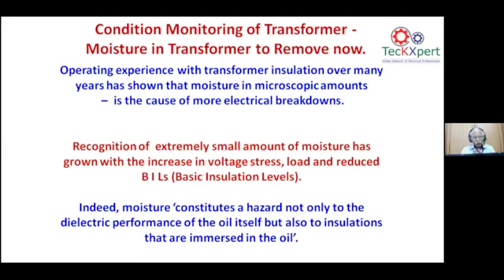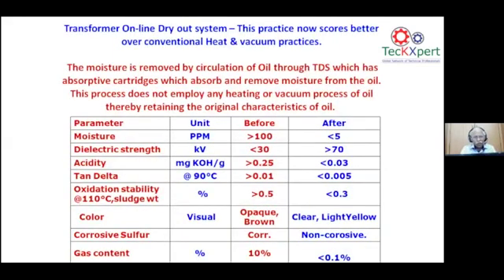More than that, it is a hazard not only to the dielectric performance of the oil, but also to the insulation that is immersed in the oil. That is why the age-old thinking is that we all go for the heat and vacuum practice of the transformer drying out system. But now the concept has changed to the transformer online drying out system, where we use cellulose type absorptive cartridges within the system, and it will be online. This will be able to remove the moisture in the transformer by the circulation of the oil and removing this moisture.